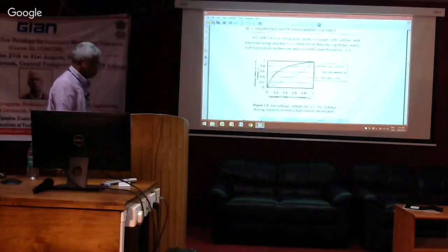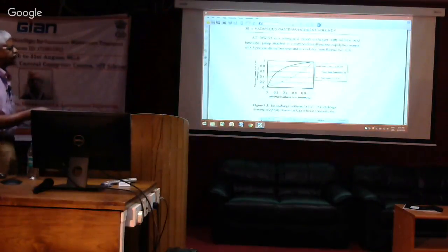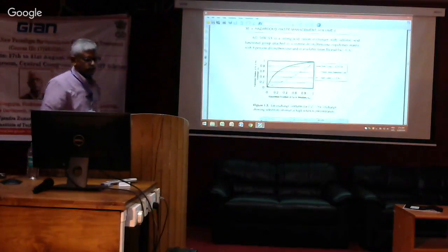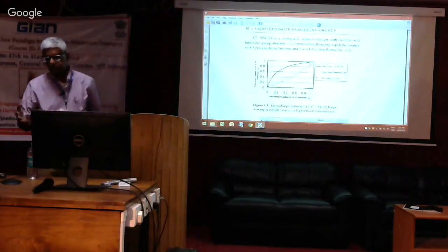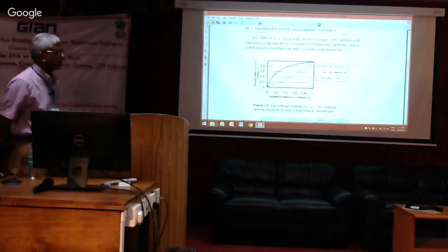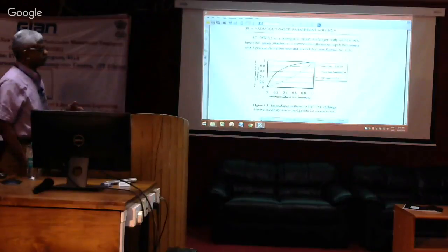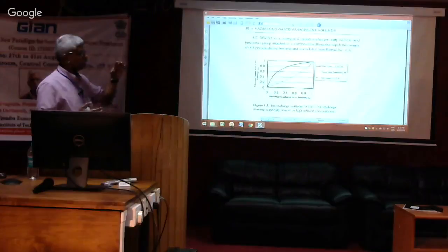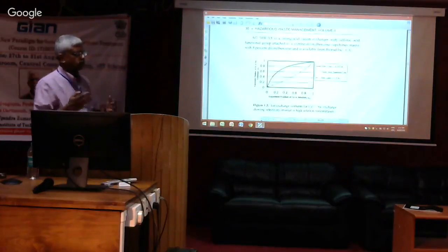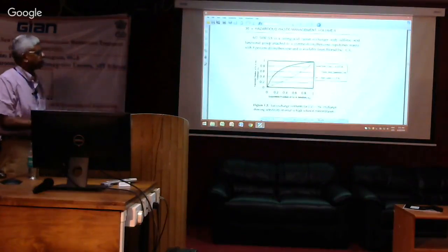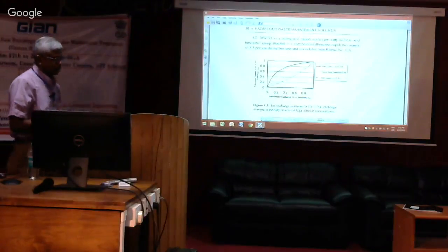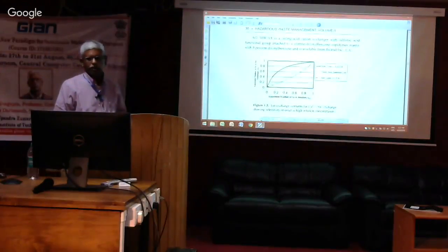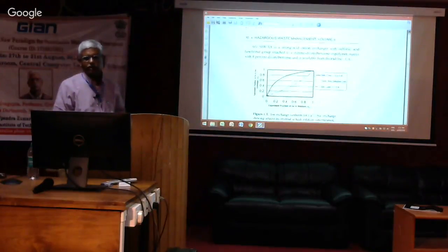And so what we do is, when we run the system, if we are trying to remove calcium, let's say we do so in water softening. In many groundwaters, we have this situation where calcium is very high, and you don't want your water to have very high calcium, because then it does not lather very well. It forms precipitates if you heat that water for your coffee or for your ironing or whatever. So you need to remove the calcium. If you want to remove the calcium, what do you do?